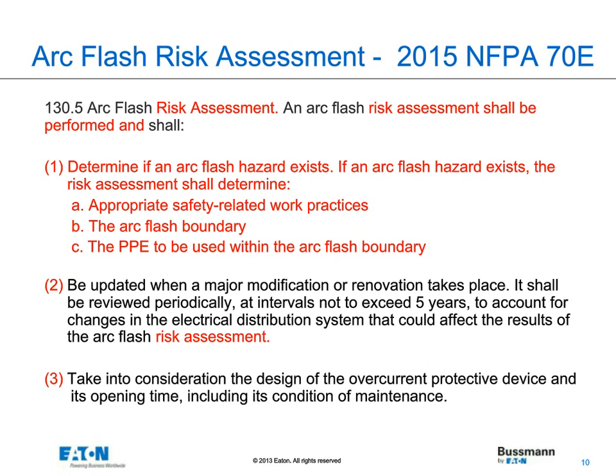Part three talks about, and there was no change here, it just talks about the condition of maintenance. And again, that was really a big issue in the past and in the current edition of 70E: we need to identify that we properly maintain equipment. If not, we really don't know what can happen with regards to the arc flash hazard.